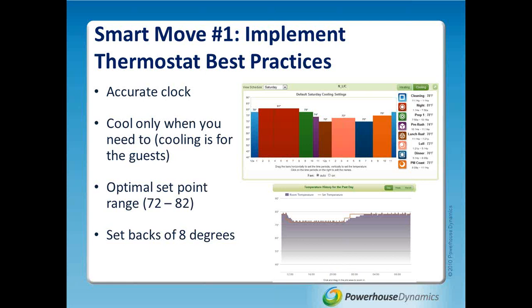There are important reasons for that, but what's key is that when setting points off your peaks and troughs, you want your target reached about an hour before you open, or 30 minutes before a peak rush. So if staff start showing up at 9am to prep, at 8am we'd have you change from the 84 degree night set point to 74 degrees in the morning.